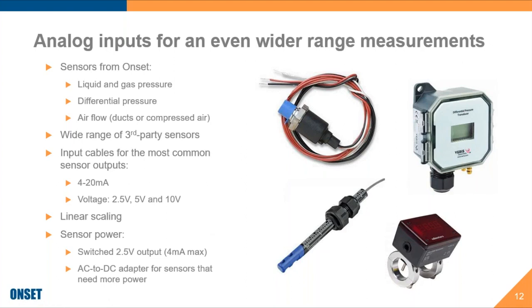sensor types. And I'm just looking here at the questions coming in. One is, will older sensors we used for the UX modules work in the self-locking inlets? Will they also self-describe? The answer to that is yes and no. Those sensors that work with the UX loggers will work fine with these new MX series analog input loggers. They won't lock into place because they don't have that locking mechanism on them, but it's got the same 3.5 millimeter jack, or maybe it's 2.5 millimeter jack. It's the same jack as used on the UX loggers, so they'll plug in just fine. And they will not self-describe because they don't have the little ID circuitry in them to tell the logger what kind of sensor they are. But they can be picked from the drop-down menu in the software, so it's easy enough to configure them.